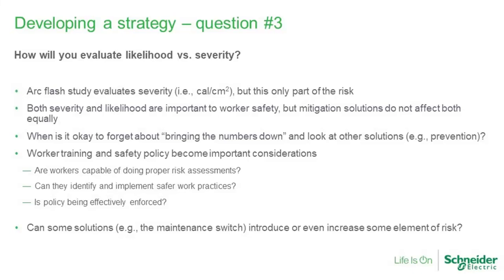That means like remote racking. That would be one where, if you're worried about protecting people from potential hazards that exist when you're inserting a withdrawable breaker back into the switchgear, remote racking is certainly a good way to go. It doesn't change the arc flash calculation. It doesn't change the value on the incident energy level. That shouldn't mean that it's a solution that just gets ignored, but realistically, that's what happens at times. So how will you evaluate likelihood versus severity? And in some cases, when is it okay to forget about bringing the numbers down and look at other solutions?